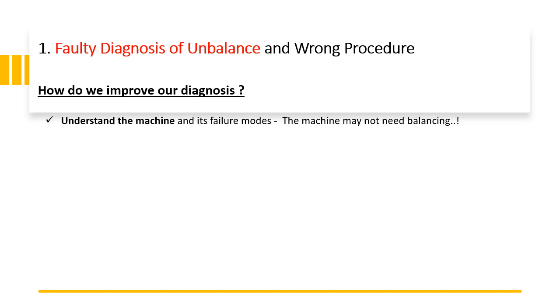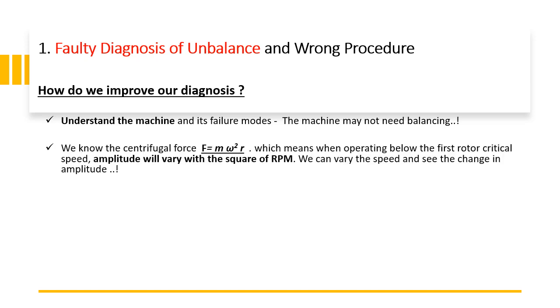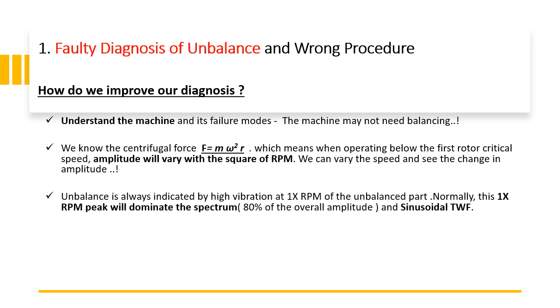To improve diagnosis, first understand the machine and its failure modes — whether it has material deposits or wear on the rotor. Second, know that centrifugal force equals m·ω²·r, meaning amplitude varies with the square of RPM — varying speed and observing amplitude change helps confirm unbalance. Third, the classic spectral indication is a high 1x RPM peak, normally 80% of overall amplitude, accompanied by a sinusoidal time waveform.